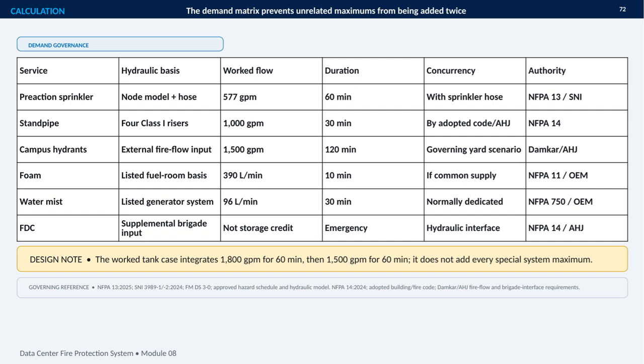The demand matrix prevents unrelated maximums from being added twice. Instead of simply summing every peak value, we identify which systems operate together and which are dedicated, supplemental, or governed by the adopted code and authority having jurisdiction. For the worked tank case, the integrated demand is 1,800 gallons per minute for 60 minutes, followed by 1,500 gallons per minute for another 60 minutes. That sequence reflects the governing scenario without treating every special system maximum as simultaneous. The final design must remain aligned with NFPA, SNI-FM guidance, the approved hazard schedule, the hydraulic model, and AHJ requirements.